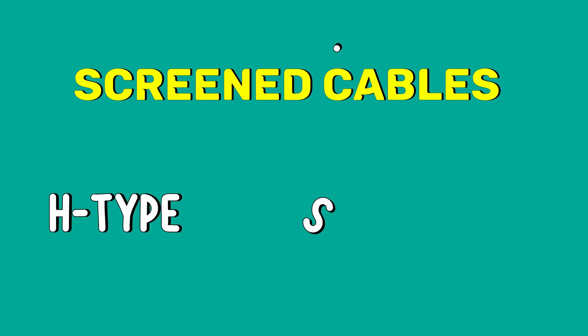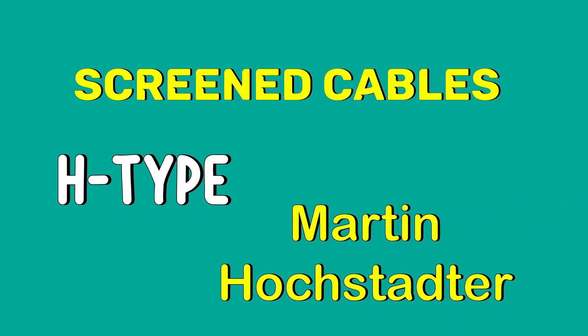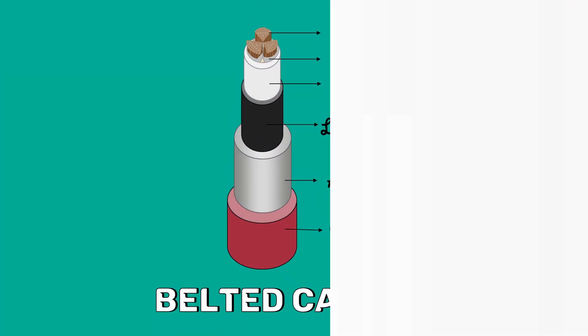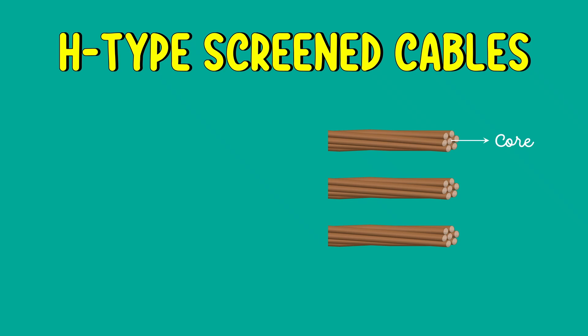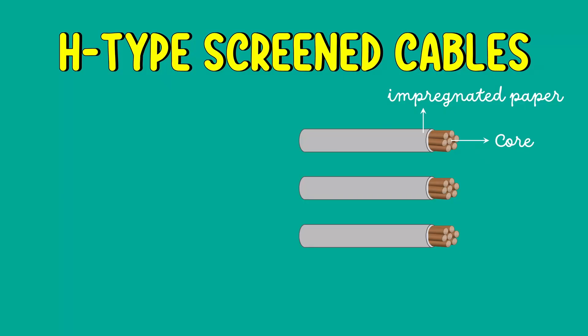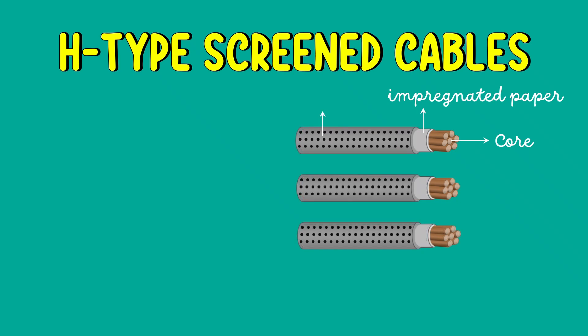There are two types of screen cables: H-type and SL-type cables. The design of H-type cable was first developed by Martin Hochstadter, which is why this type is called H-type cables. In order to reduce the electrical stress, he made a small modification in the construction of belted cables. Similar to belted cables, screen cables have three cores insulated from each other by layers of impregnated paper.